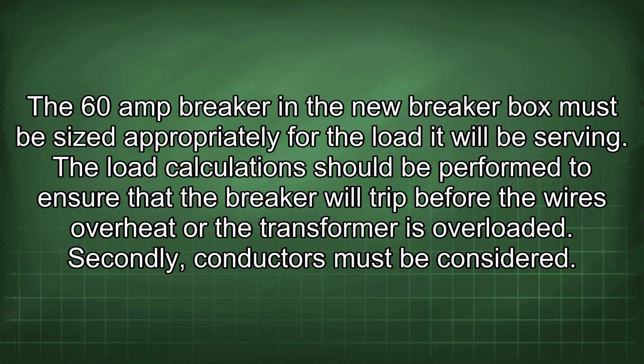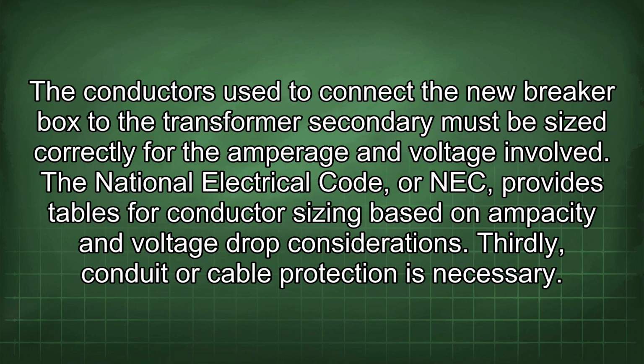Secondly, conductors must be considered. The conductors used to connect the new breaker box to the transformer secondary must be sized correctly for the amperage and voltage involved. The National Electrical Code, or NEC, provides tables for conductor sizing based on ampacity and voltage drop considerations. Thirdly, conduit or cable protection is necessary.